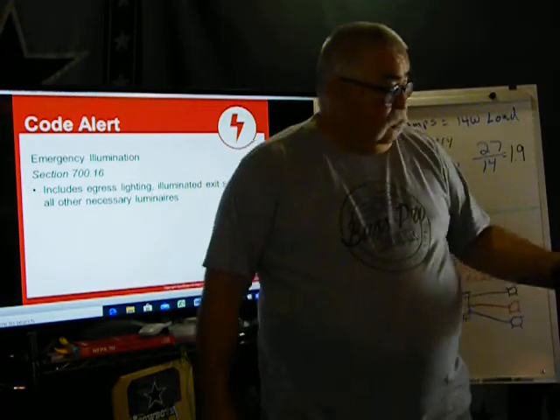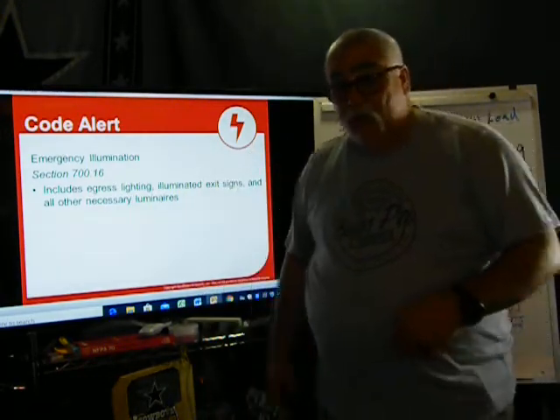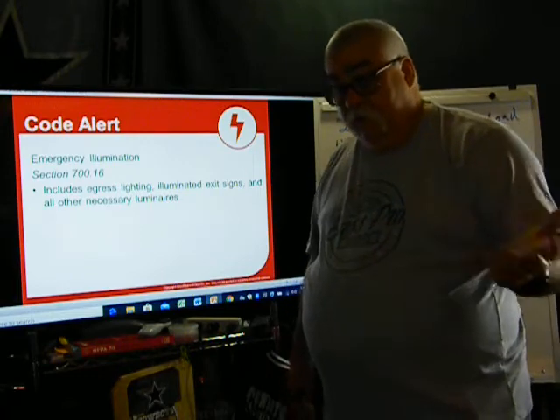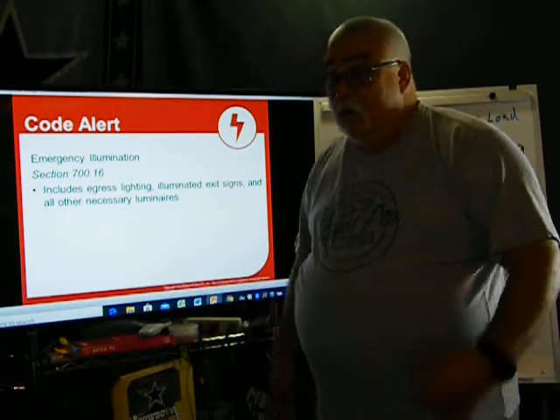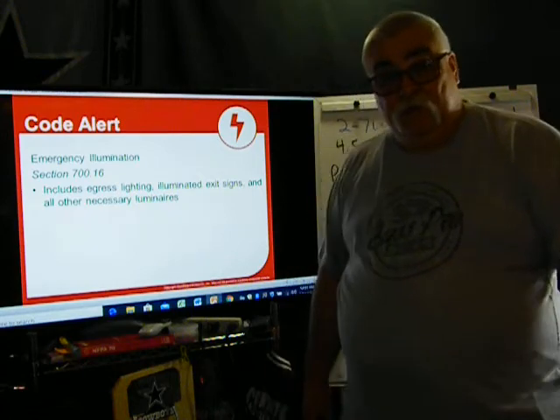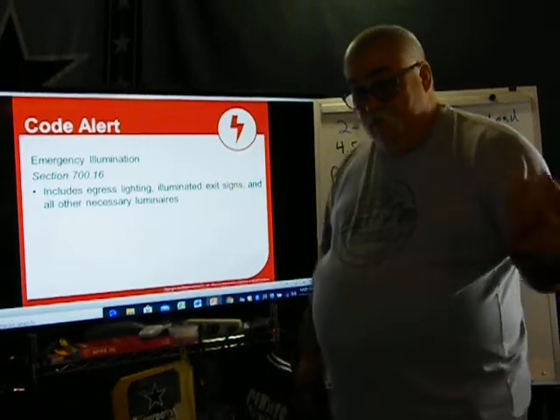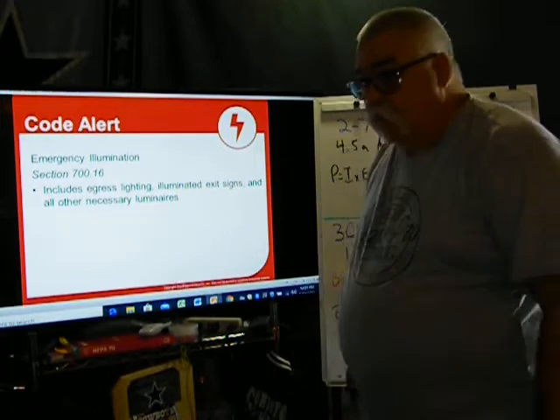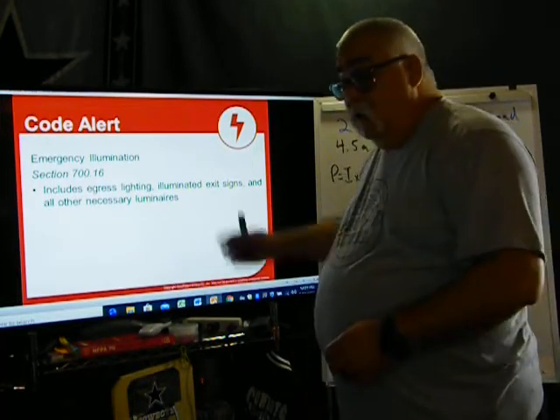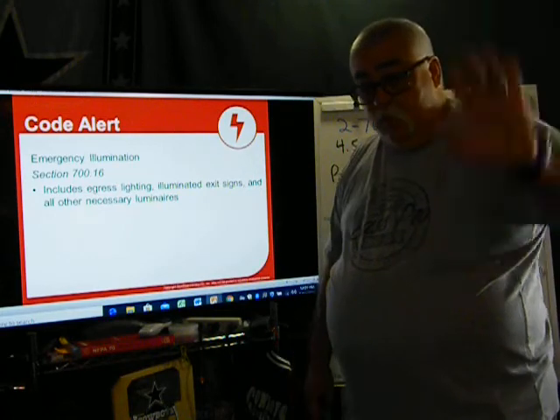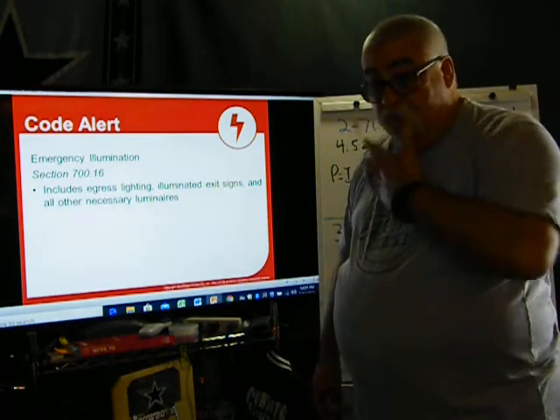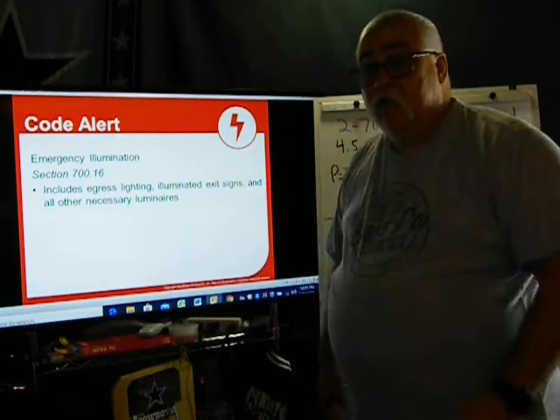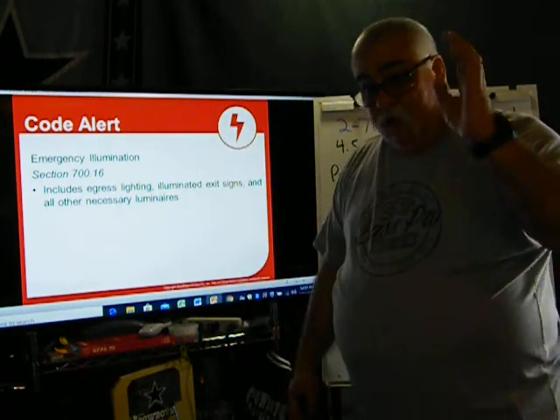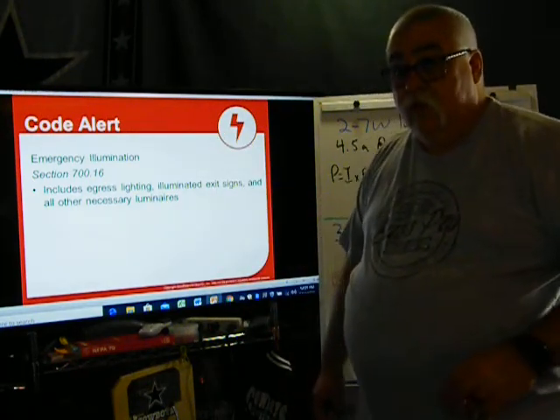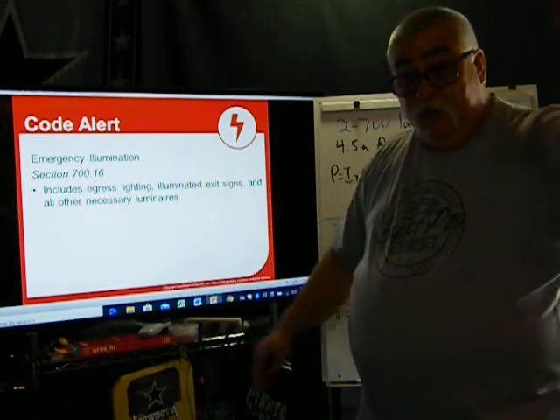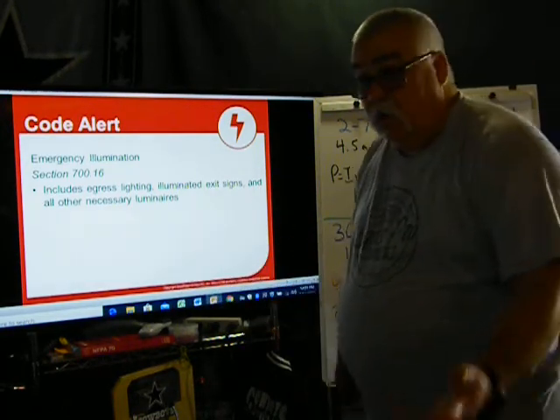If you're using batteries or emergency lights that have a battery inside, that light's got to stay on for an hour and a half so people can exit. If you've got a generator, the generator's got to run. It's got to stay on at least an hour and a half. So you've got to make sure you're checking the levels on the fluids so the generator runs for at least an hour and a half. That's all sizing, and you size the generator to turn on. Again, like I showed you yesterday, we only have a sub panel that controls certain lighting: one light in every room, lights in the hallway, lights in the stairwell, and then maybe some outside lights so people can exit and then they're outside, not in the dark in case it happened at night.